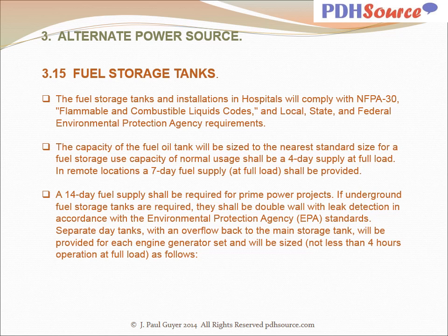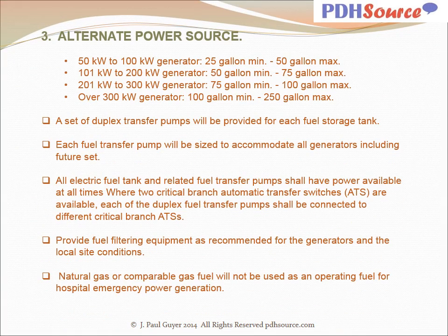Separate day tanks with an overflow back to the main storage tank will be provided for each engine generator set and will be sized not less than 4 hours operation at full load as follows. 50 to 100 kW generators, 25 gallon minimum, 50 gallon maximum. 101 kW to 200 kW generators, 50 gallon minimum, 75 max. 201 kW to 300 kW generators, 75 gallons minimum to 100 gallons max. Over 300 kW generators, 100 gallons minimum, 250 gallons maximum.